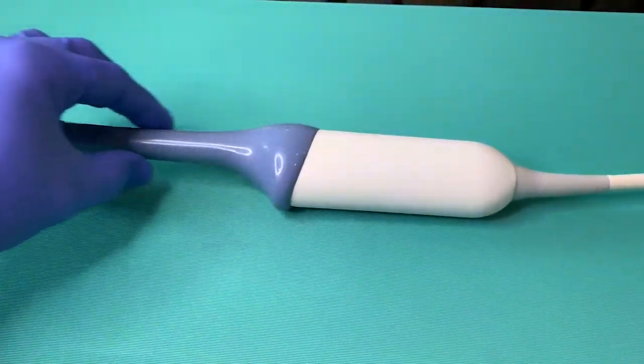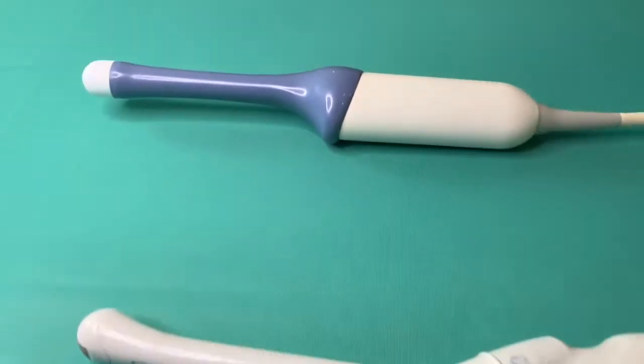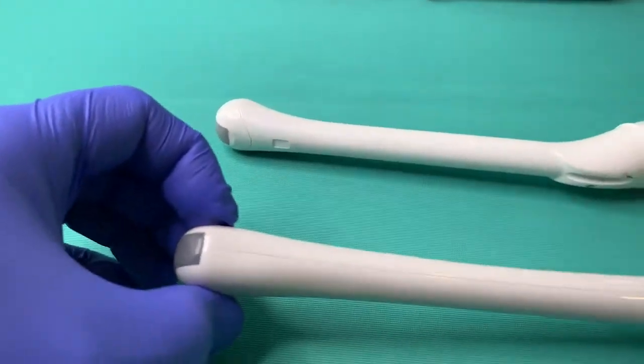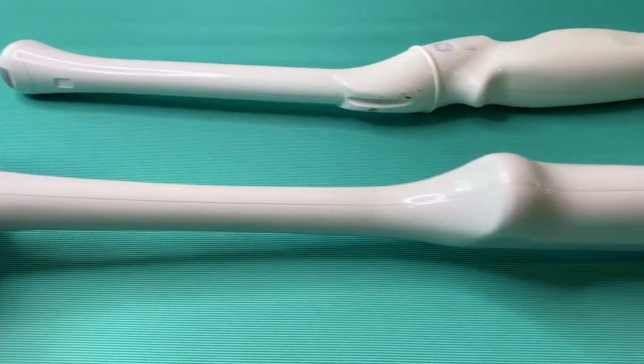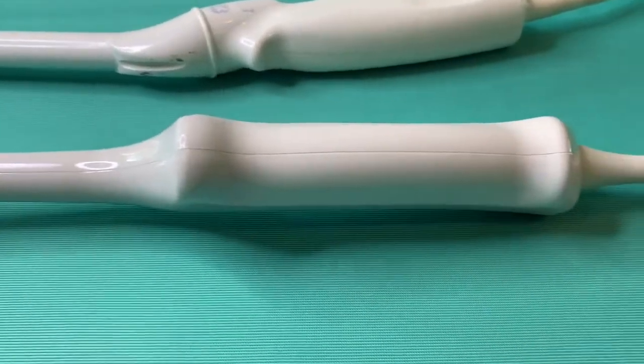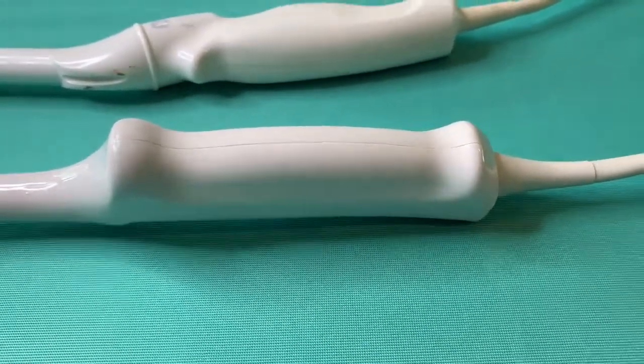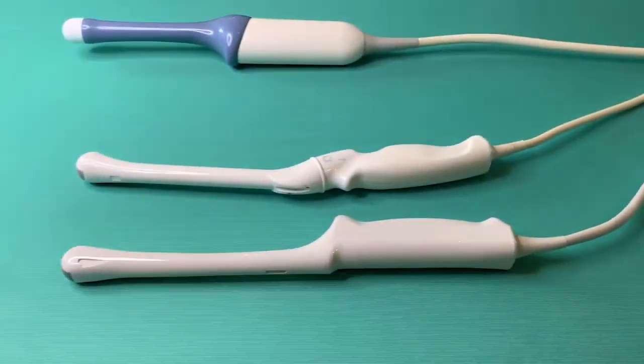Intercavity probes are high-level disinfected by immersion or vapor chamber. Solid, quality seals are of utmost importance on these probes. Any area on any probe that is believed would allow fluid entry should be addressed with a high priority.